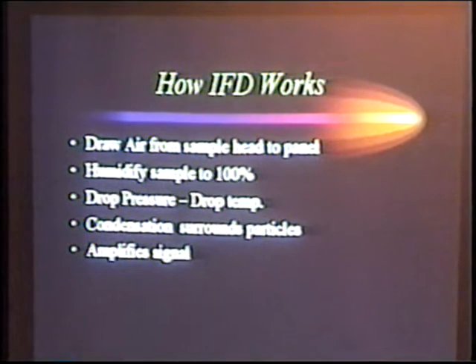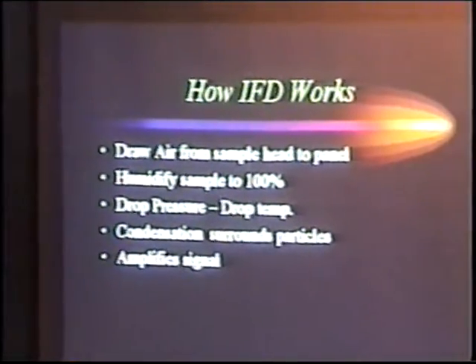This control panel has a little tiny chamber, and it has a water source in the panel as well. Once the sample is in the chamber, it is humidified to 100%. Then the sample is subjected to a vacuum. At that point, we drop the pressure inside this chamber. Dropping the pressure creates a drop in temperature. With the humidity in the chamber, we get condensation. The condensation surrounds the invisible particle. Now the invisible particle has been amplified. To make that a little simpler, the end result is basically a cloud.